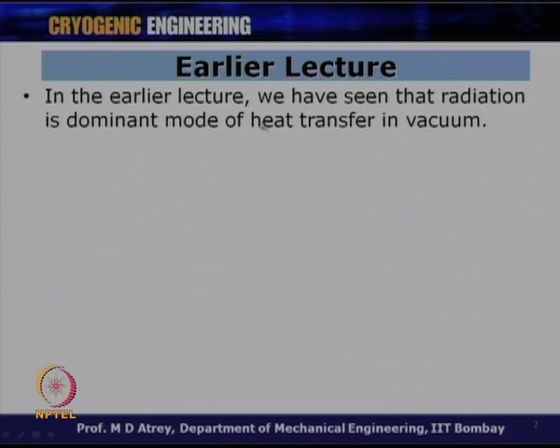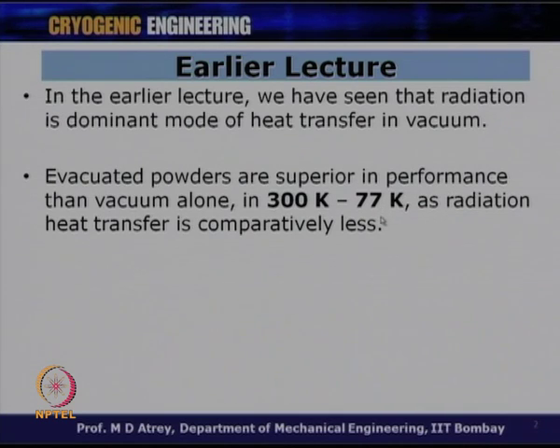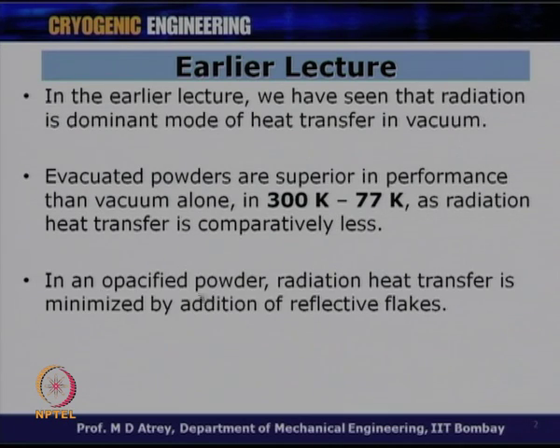In the earlier lecture, we had seen that radiation is the dominant mode of heat transfer in vacuum. We found that evacuated powder is superior in performance to vacuum alone in the temperature range of 300 K to 77 K, that is liquid nitrogen temperature. Below 77 K, radiation takes over and we need to look for other insulation methods.